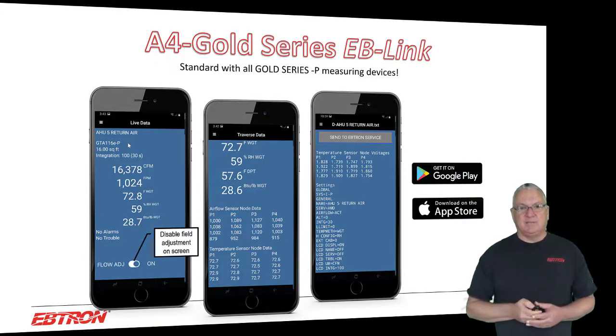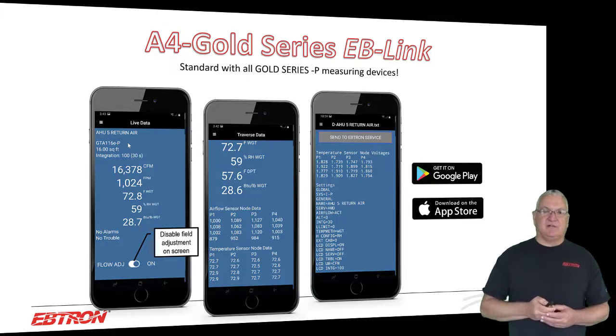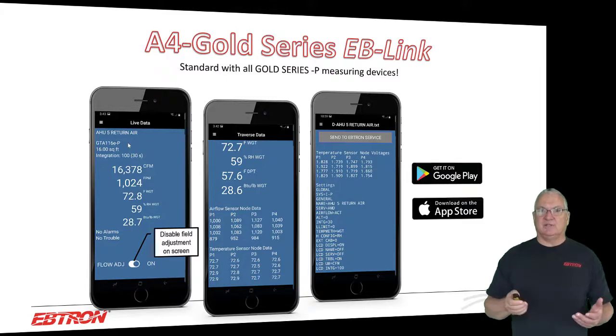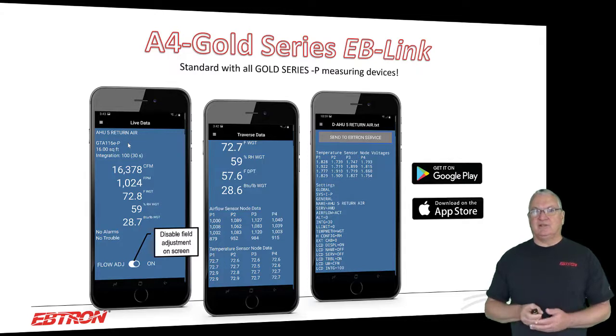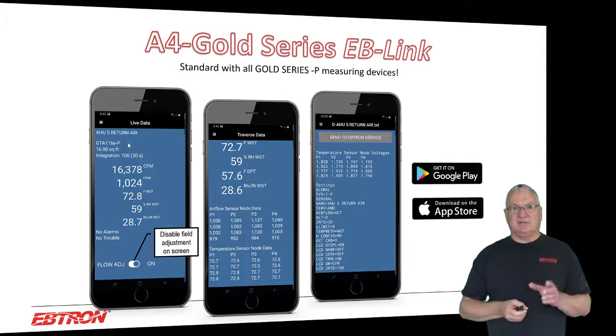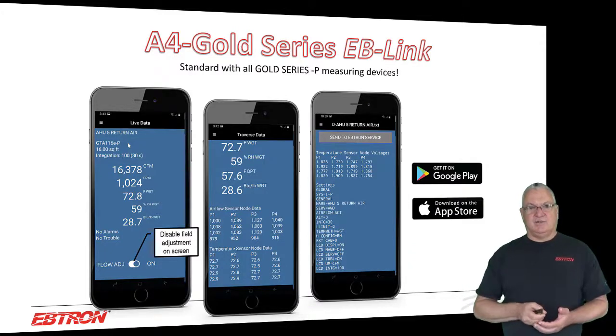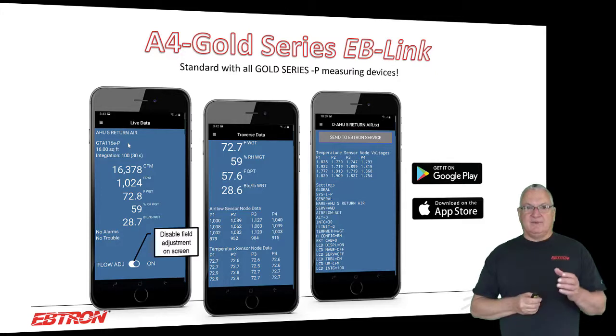The other thing that's really good about it is, as we've talked about in other presentations, sometimes folks will adjust our flow meter, and you want to go see what the flow meter really read if they did do that adjustment. You shouldn't disable it at the transmitter, because if you do and the control system was tweaked to work with these corrections, you could really screw your building up. So you use the EBLink reader and you just turn flow adjustment off, and you'll see the unadjusted airflow rates.